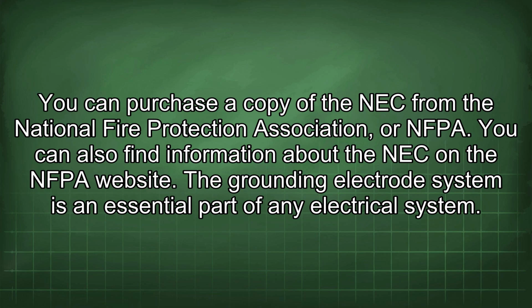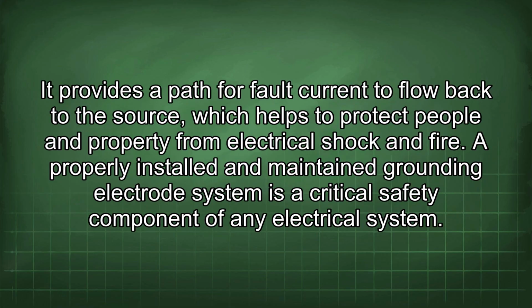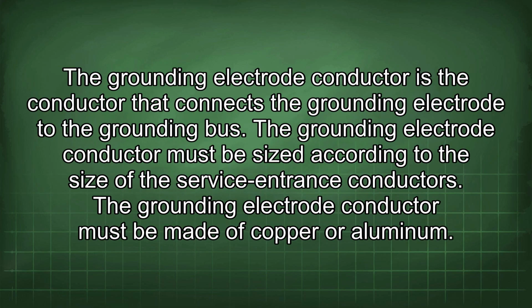The grounding electrode system is an essential part of any electrical system. It provides a path for fault current to flow back to the source, which helps to protect people and property from electrical shock and fire. A properly installed and maintained grounding electrode system is a critical safety component of any electrical system. The grounding electrode conductor is the conductor that connects the grounding electrode to the grounding bus. The grounding electrode conductor must be sized according to the size of the service entrance conductors.